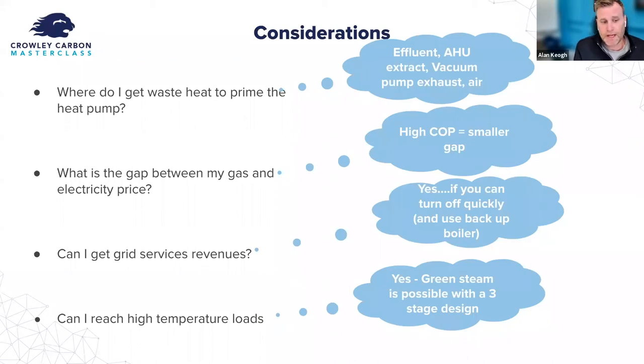And then thirdly, can I actually use the heat pump to access grid service revenues? Colin will talk about this later, but DSU, DS3 revenues - if you can turn off your heat pump at very short notice and then use your boiler, existing steam or gas-fired boiler, to make up your steam supply or your LPHW supply, then that could become an asset that can generate grid services revenues.